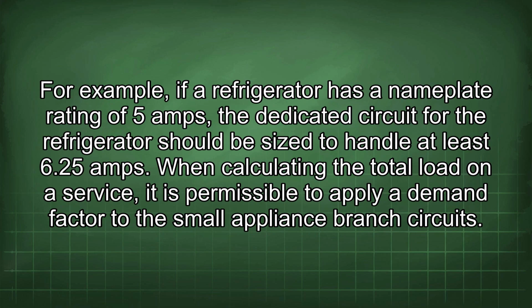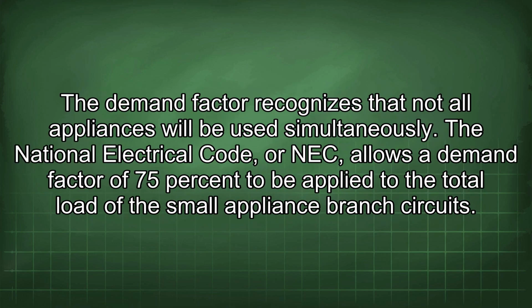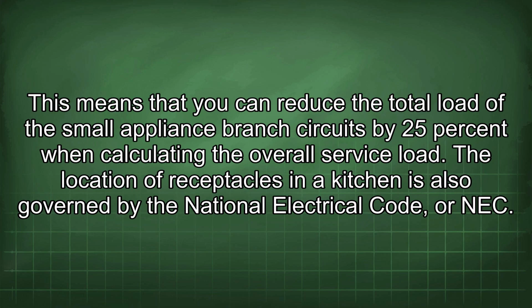For example, if a refrigerator has a nameplate rating of 5 amps, the dedicated circuit for the refrigerator should be sized to handle at least 6.25 amps. When calculating the total load on a service, it is permissible to apply a demand factor to the small appliance branch circuits. The demand factor recognizes that not all appliances will be used simultaneously. The National Electrical Code, or NEC, allows a demand factor of 75% to be applied to the total load of the small appliance branch circuits.